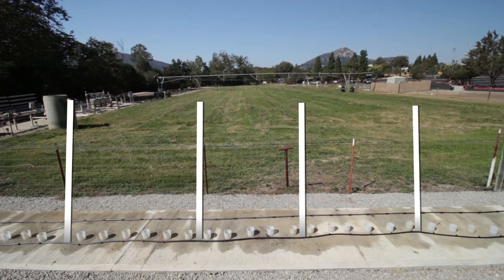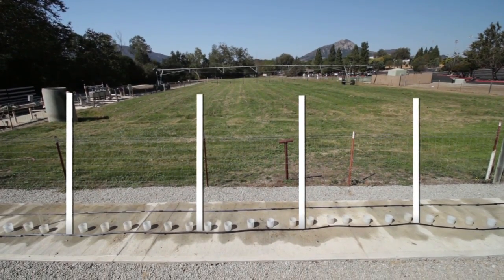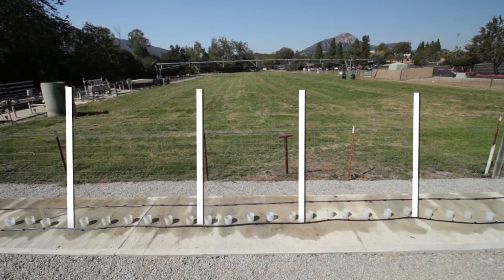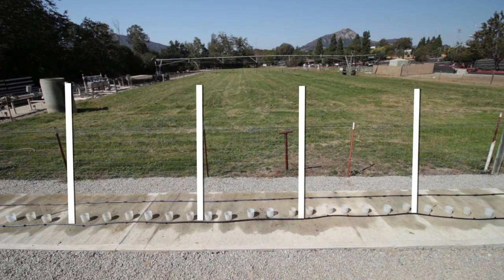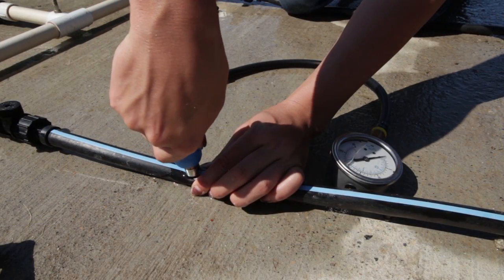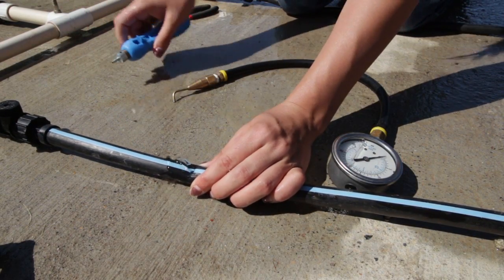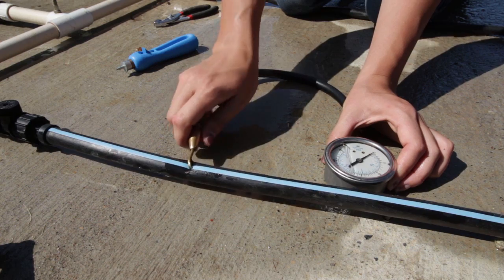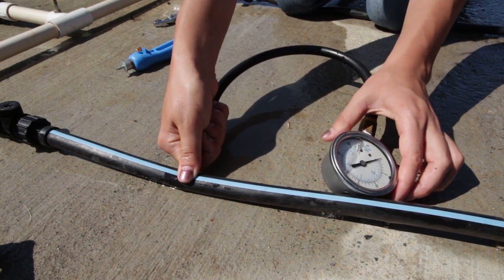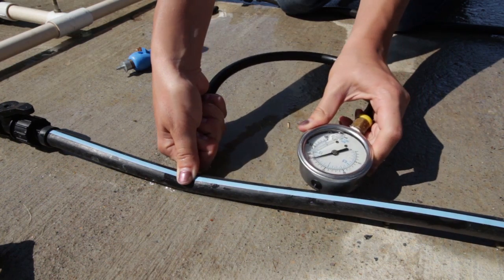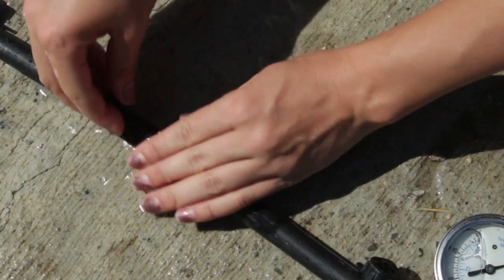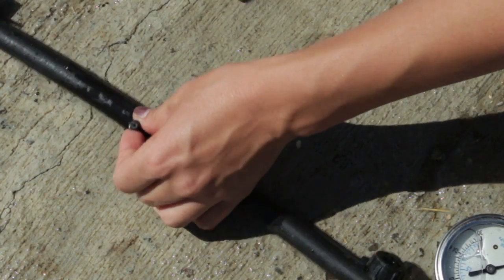The second part of the evaluation is to measure the pressure throughout the hose. Pressure measurements should be taken from 4 evenly distributed points throughout the hose. Begin by using a punch and punching a hole into the hose. Next, carefully insert the pitot tube into the hole with the opening of the tube facing upstream. Once you've recorded the measured pressure reading, plug the opening using a goof plug and pliers.